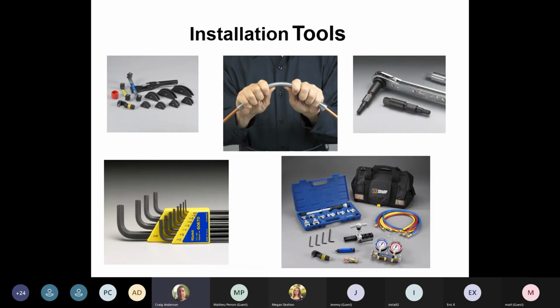So installation tools for you that are out there. We have benders, spring benders. We have the Ritchie crank benders. We have Allen keys, and then you'll have your service wrench up here in the right corner. Service wrench is great for doing your valves outside. I recommend you take your Allen key first, get it in there, do your first little crack with your Allen key, and then putting your service wrench on it. The service wrenches tend not to get into that service valve deep enough all the time.